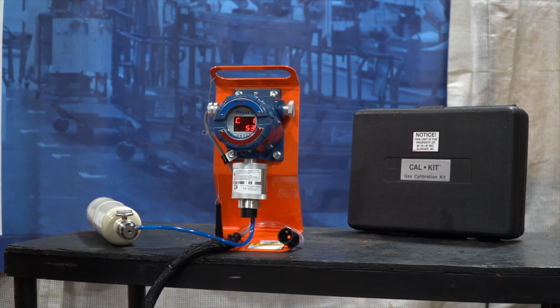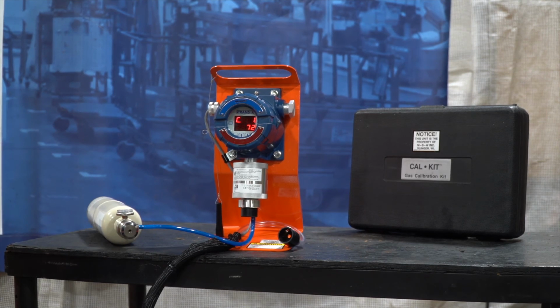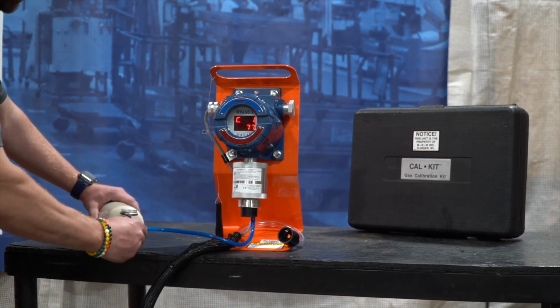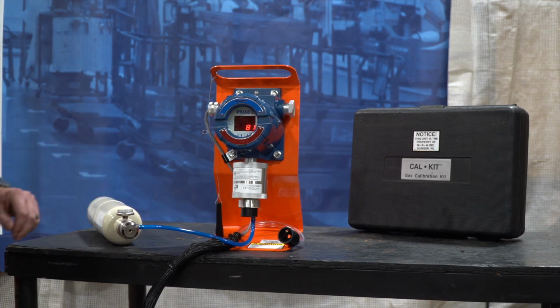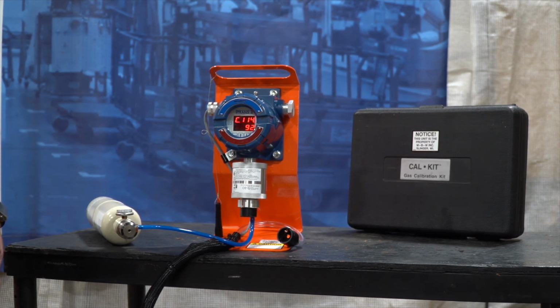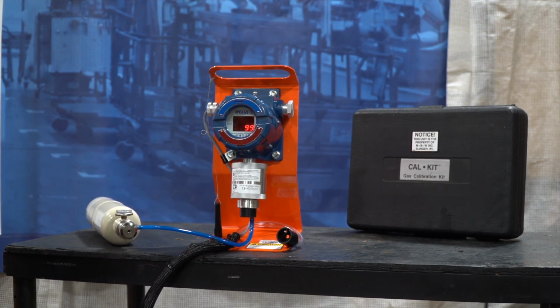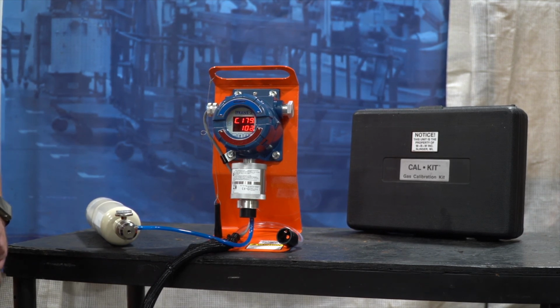And once again, we're waiting for it to count up to 75. So when it hits 75, I will turn on the calibration gas. And now I will turn on the gas, and you're going to see the number on the upper right that is flashing go up. That is the gas going through the sensor head and is beginning to do the calibration process. One thing to note is if you do not have the calibration gas and you enter the C for calibration, you will want to unplug the sensor from the machine and it will reset. And it will not harm the sensor itself.